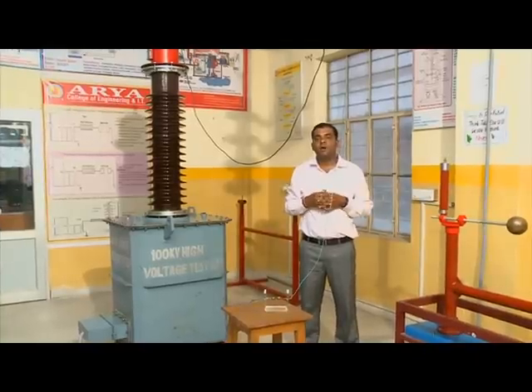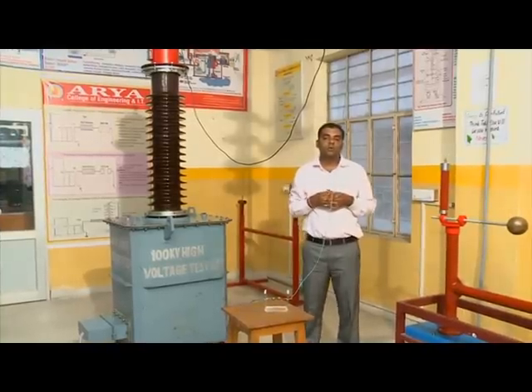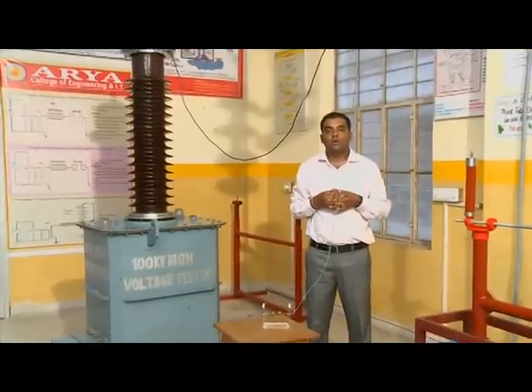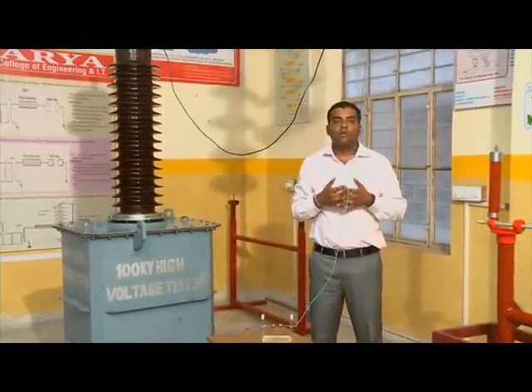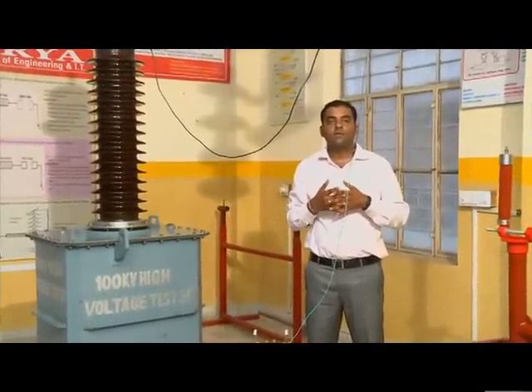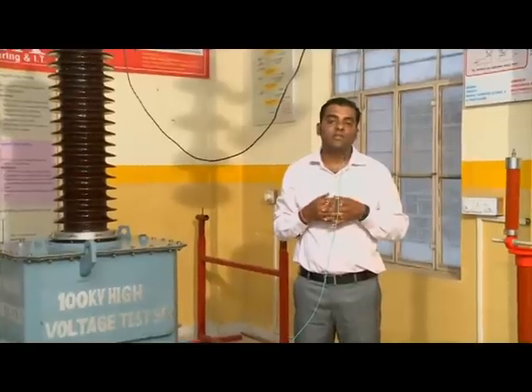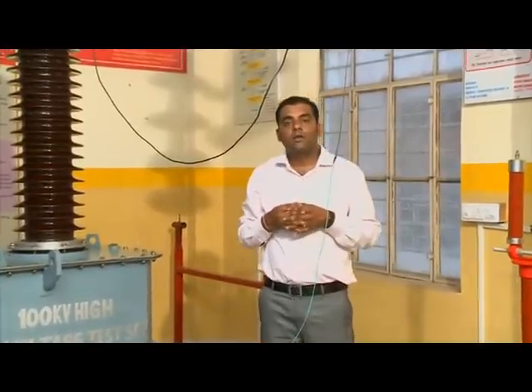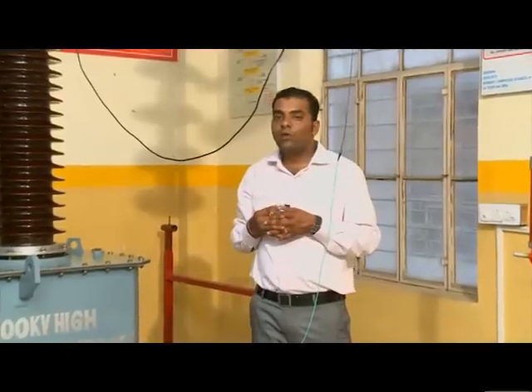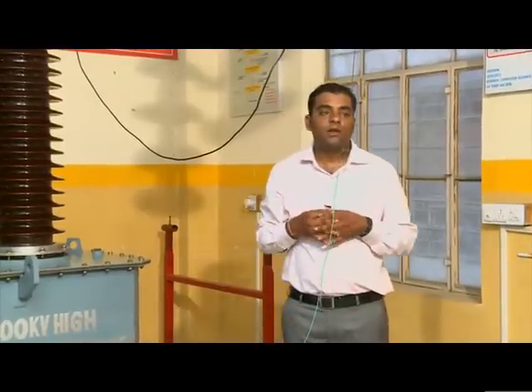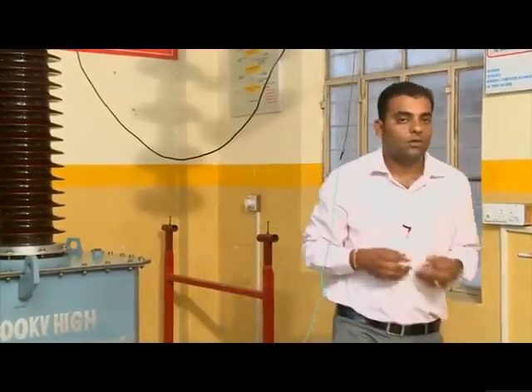Eta equals spark over voltage of the insulator string upon N into spark over voltage of the individual unit. After the calculation of this formula, we can find out the efficiency of the insulator string. To find out the value of spark over voltage, we will perform the practical with the help of the control panel.